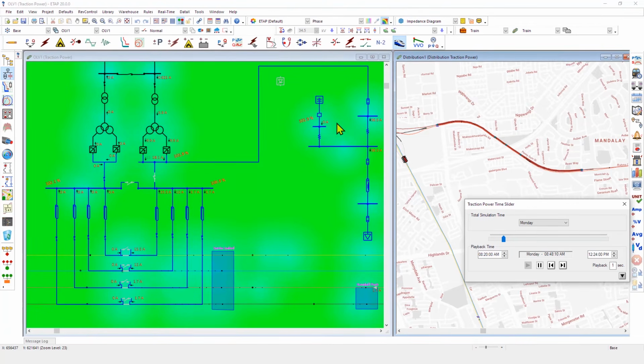By adjusting the BMS and the state of charge settings, you can fine-tune the battery energy storage such that you are charging and discharging at appropriate moments and essentially conserving energy. So when the train is accelerating, you can set up the battery to discharge and supply additional power and eliminate the AC demand in the system. And when the train is braking or is capable of regenerative braking, you can absorb that energy and charge the battery at the same time.